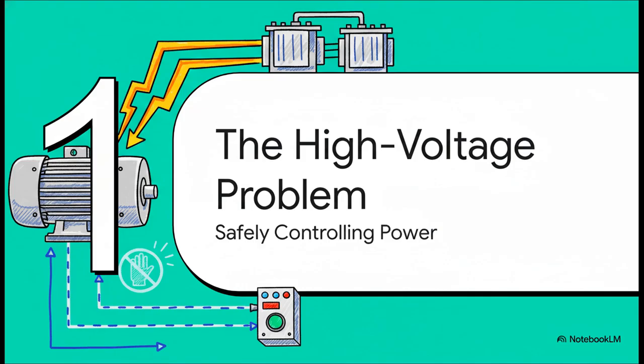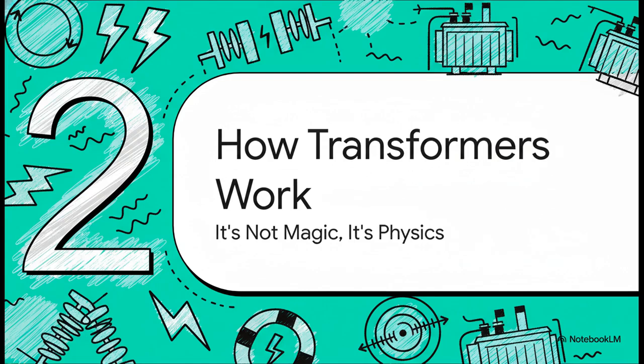And that really gets to the heart of the problem we're solving here. See, the big motors, the heavy machinery, they need a ton of power, often running on something like 480 volts. But you would never, ever want an operator's finger anywhere near a start button with 480 volts crackling behind it. So we've got to find a way to keep that high-power world completely separate from the low-power control world. So how do we do it? Well, the elegant solution to this whole high-voltage problem is the transformer. It's this amazing device that bridges that voltage gap safely and super efficiently.